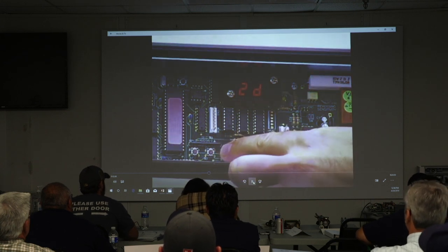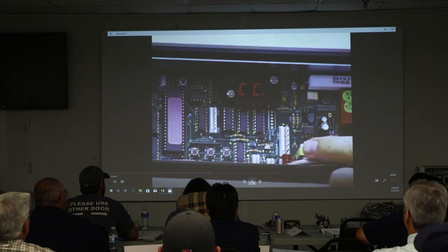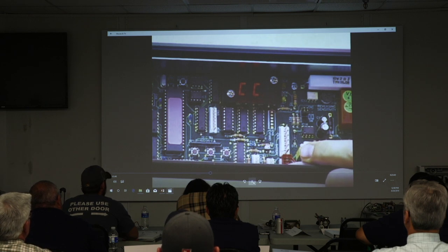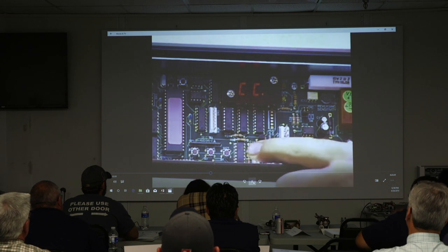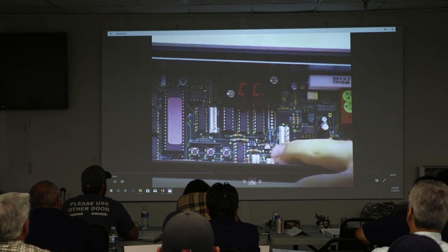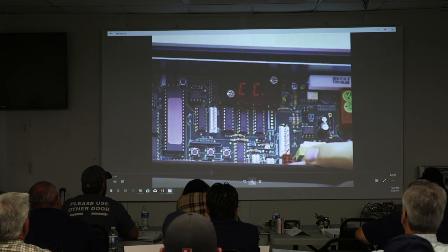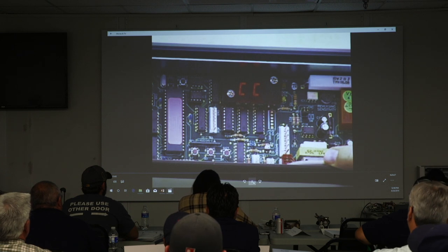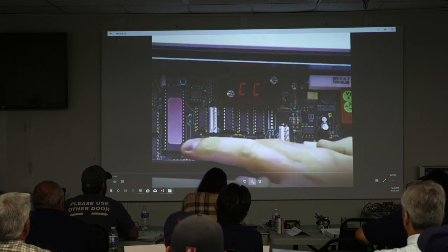Double-clicking the set button is a shortcut to parameter access. The blinking decimal point is the same, but the toggle LED remains on. With the display in the program mode, press and hold set to display the current value of the parameter. If no changes have been made since initialization, these values will be the factory default. To change value, press up or down while holding the set button until desired value is displayed.